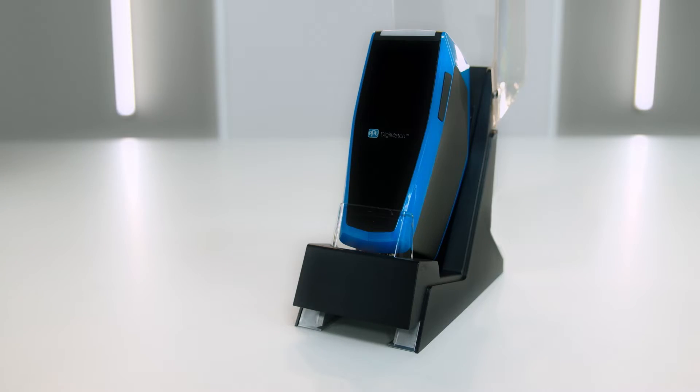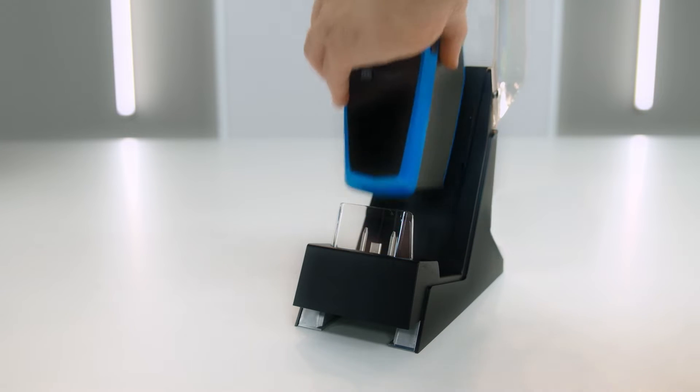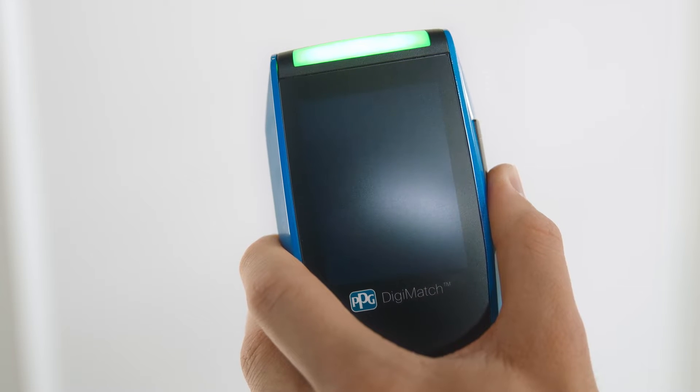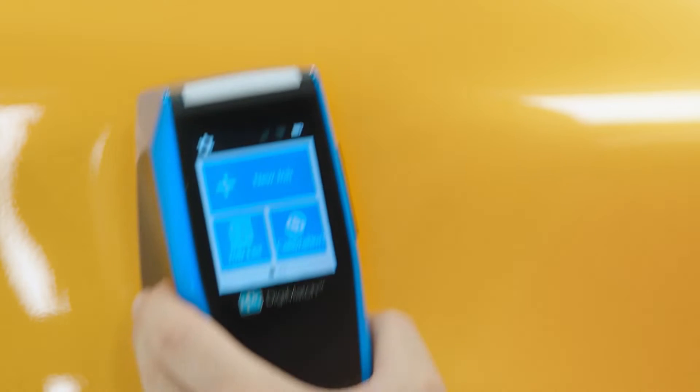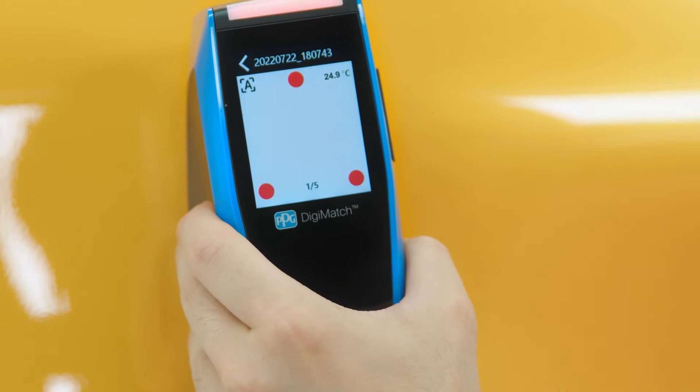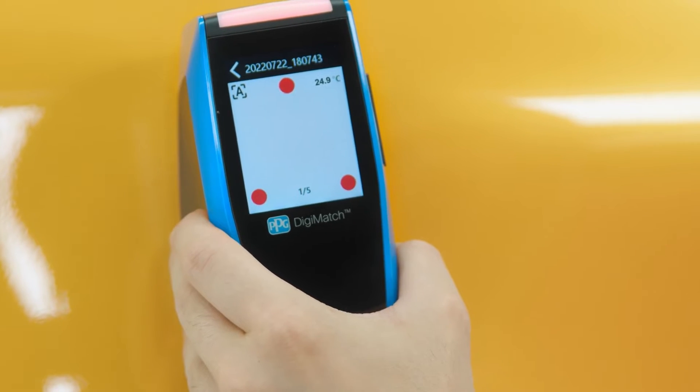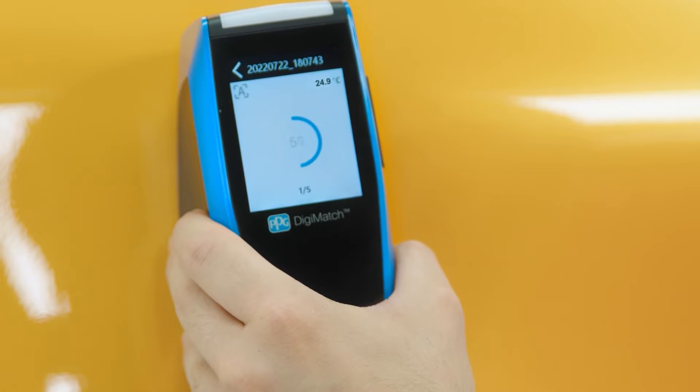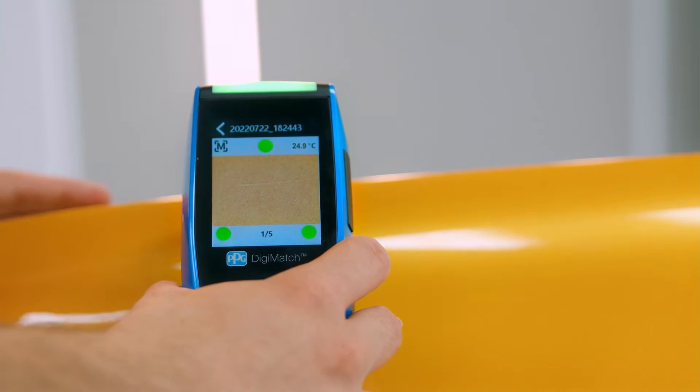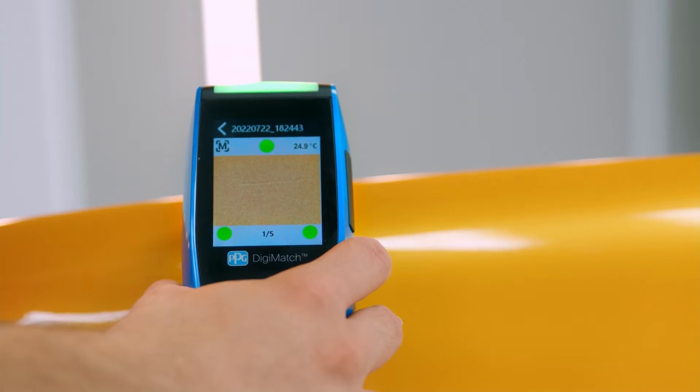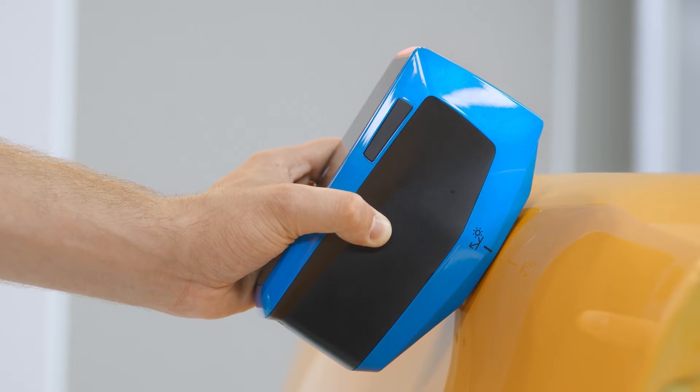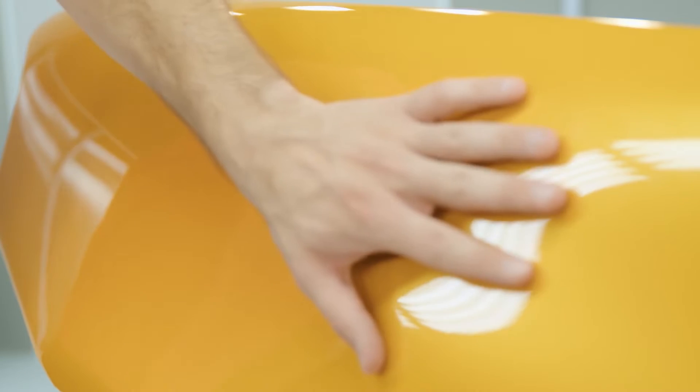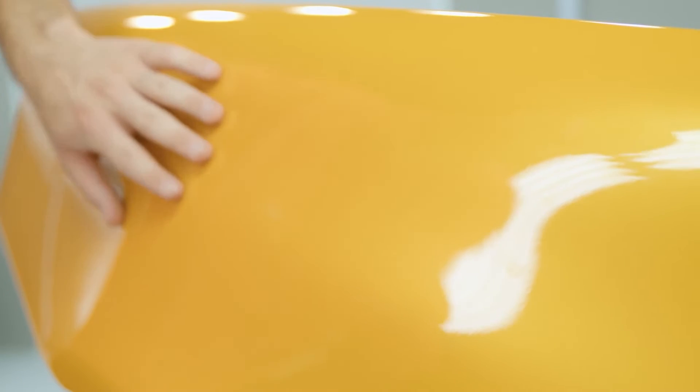To start reading the color, remove it from the docking station and check that it is turned on. From the PPG Digimatch main screen, tap the new job icon to start the measurement process. Keep in mind that even though the PPG Digimatch has enhanced features to make readings on a curved surface possible, your best outcomes are achieved on a flat surface. So when possible, measurements should be made on the flattest part of a sample.